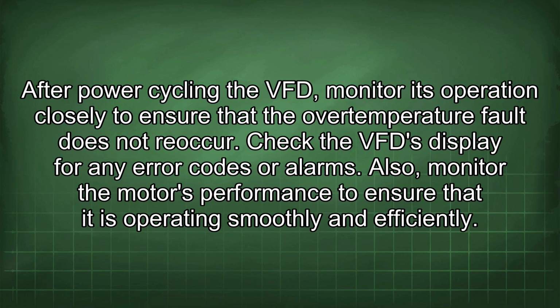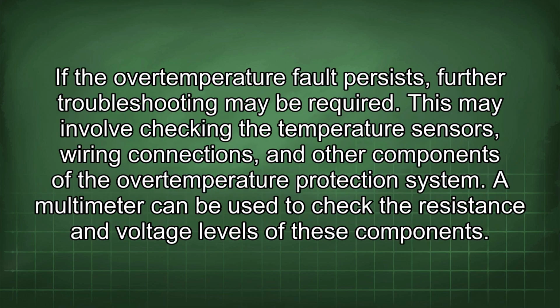monitor its operation closely to ensure that the overtemperature fault does not recur. Check the VFD display for any error codes or alarms. Also, monitor the motor's performance to ensure that it is operating smoothly and efficiently. If the overtemperature fault persists, further troubleshooting may be required.